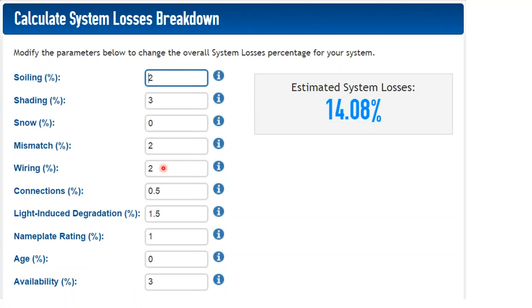You calculate voltage drop by looking at the distance of the furthest cable run back to the inverter, and you want that to be less than a 2% voltage drop, because this is just linear efficiency that you're going to lose off the top of your solar production. The minimum code is like 3% now for voltage drop, so it's just cost effective to upsize your solar cables. A common practice would be, if your MC cable can take number 10, you run number 10 back to the inverter. If your inverter output can take a larger conductor, and your tap conductor can take it, then go ahead and upsize your cable where appropriate.